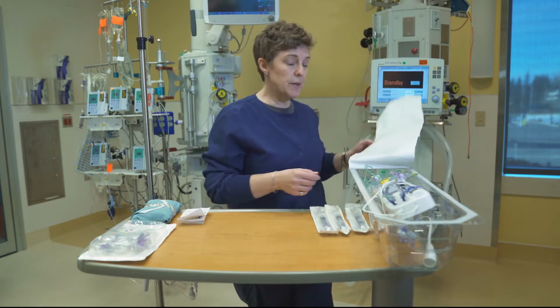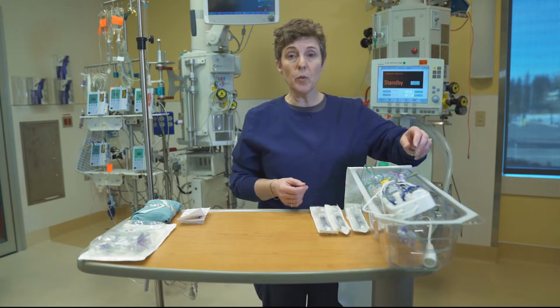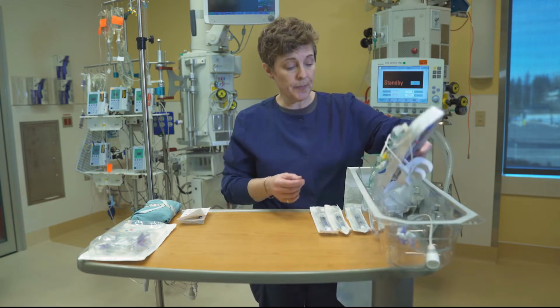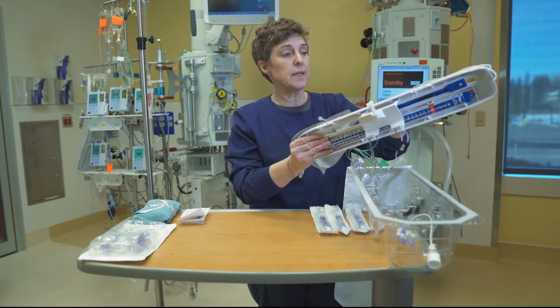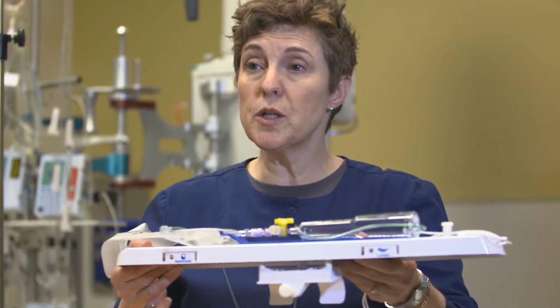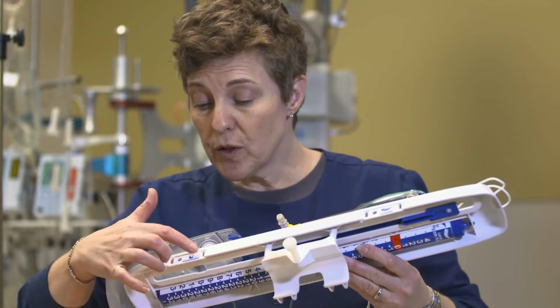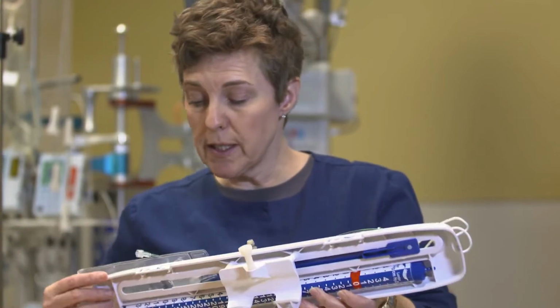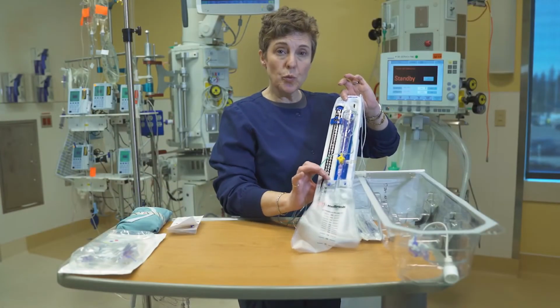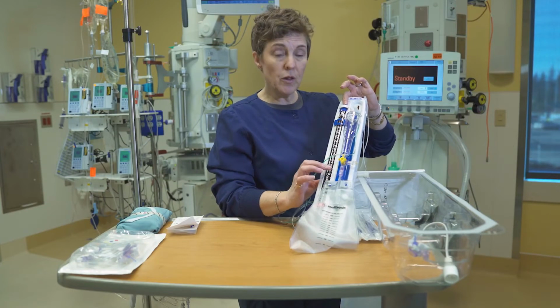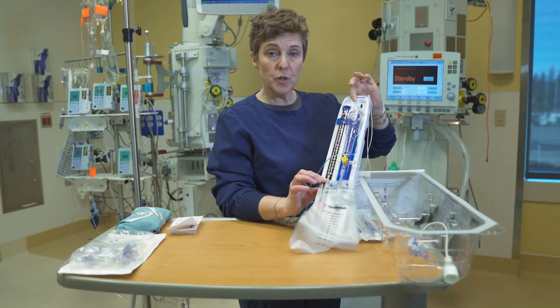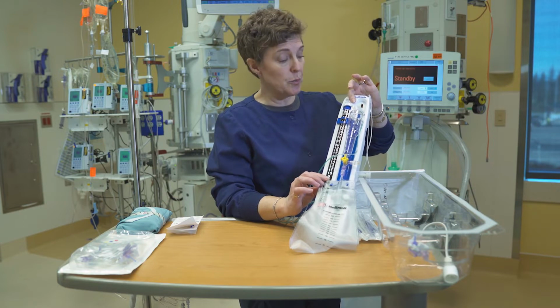When you open your system, there are a few things to remember with the ventricular drain that are important. The first is that you need to know where you're going to be monitoring, whether that's going to be ventricular, which is what we're going to be doing today, or whether that's going to be lumbar. On this system, it's very clearly indicated with a little head and a little lumbar spine. So make sure that you get the right one. So once you've established which area you're going to be monitoring, the other part is to know which measurement you're going to be using and choosing the correct place that you're going to be doing it.